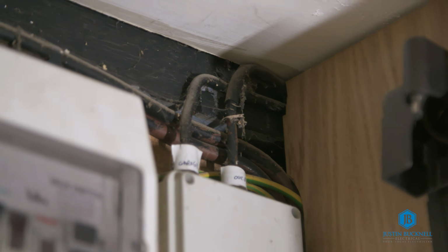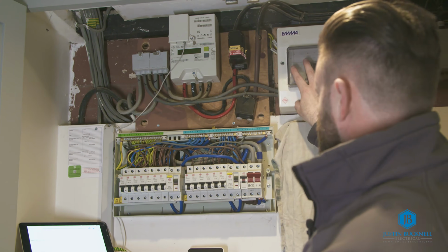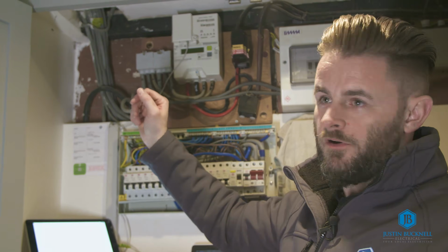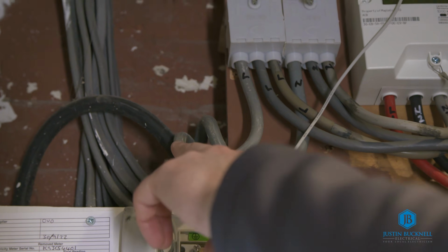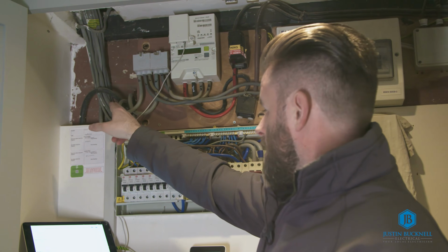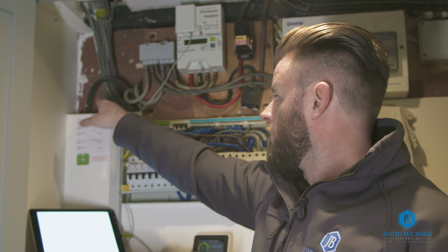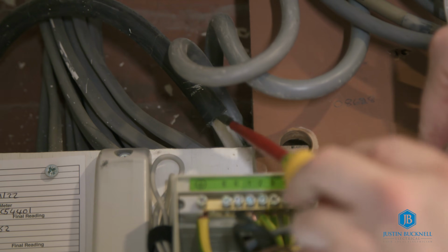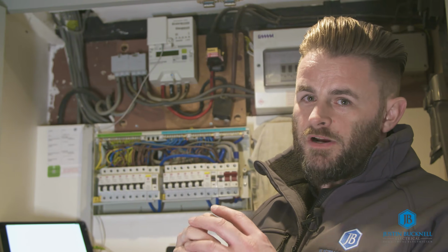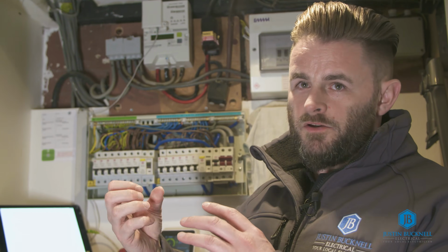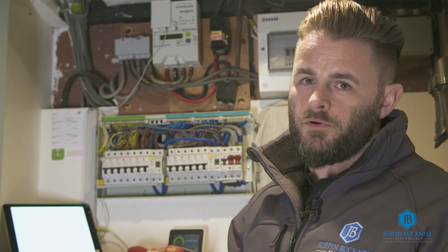A couple more observations that we made is that the mains tails are only 16mm feeding this consumer unit, and they should be 25mm. The ones feeding this consumer unit are of the correct size. Another observation that I've seen is that the feed going out to the outbuilding, which is run from here in armoured cable, is not being glanded off at all here, and we've checked down the other end and it's also not being glanded off there at all. So that means the strands on the first inside PVC sheath of the SWA cable are not earthed at either end, and that is a bit of a problem in terms of safety.